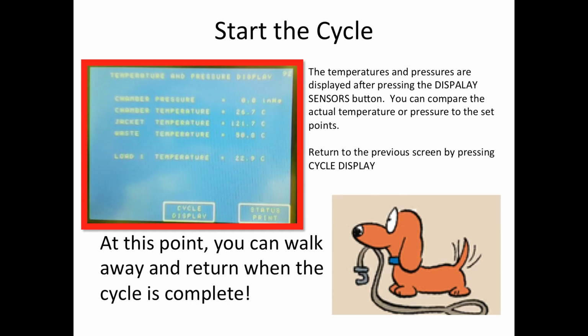The chamber temperature, the load temperature, all of these things are displayed when you press the Display Sensors button. So you can compare the actual temperature or pressure to the set points and know where you are in the individual phase of a cycle. And when you are done checking those things, you can return to the previous screen by pressing Cycle Display. At this point, you can walk away and return when the cycle is complete.